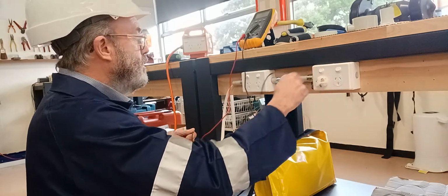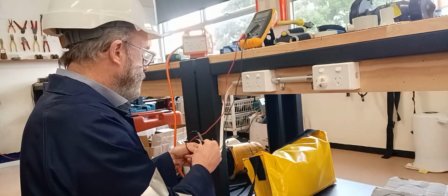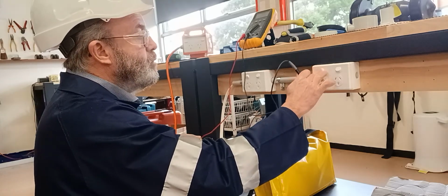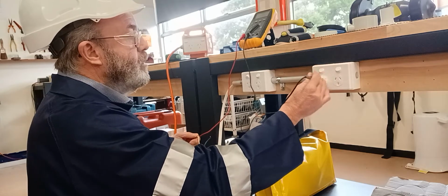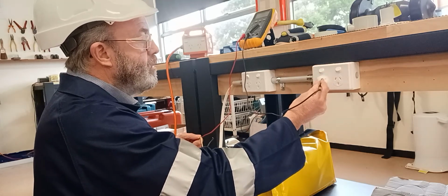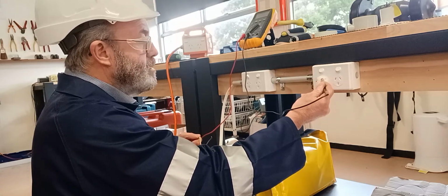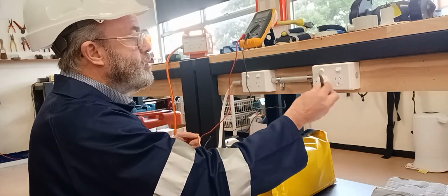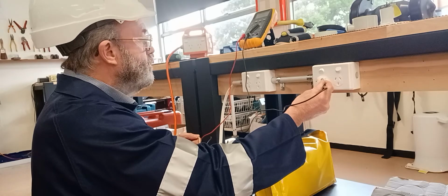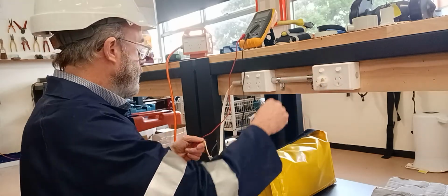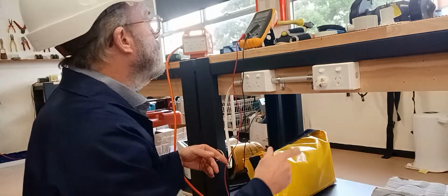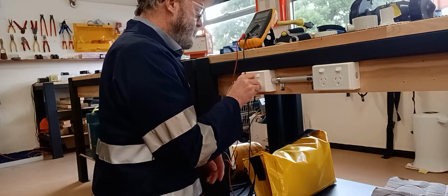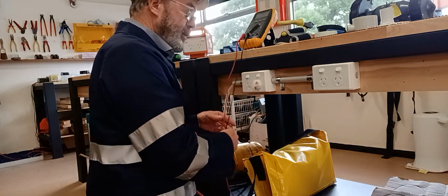That's good. My third test is the earth. Turn the switch on, try the active pin, no. The neutral pin, no. Earth pin, and yes, we've got a termination. So it's all good. The switch on, it's still all good. Okay. Got to do the same for the other power point on the other side. So we pull the plug out, go to the other power point, and do the same thing again.